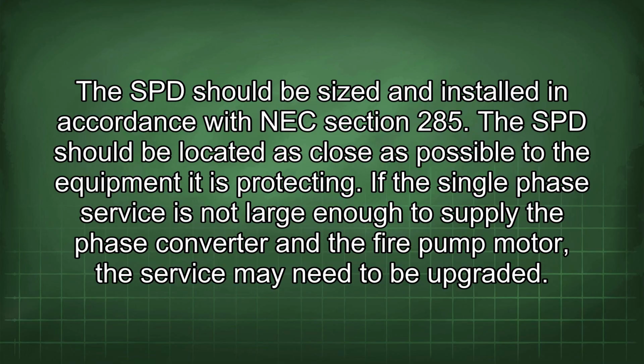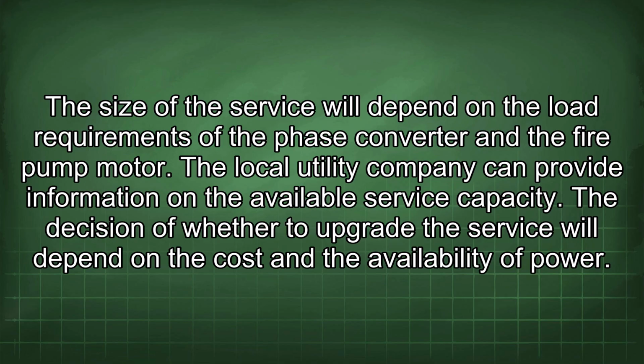If the single-phase service is not large enough to supply the phase converter and the fire pump motor, the service may need to be upgraded. The size of the service will depend on the load requirements of the phase converter and the fire pump motor. The local utility company can provide information on the available service capacity. The decision of whether to upgrade the service will depend on the cost and the availability of power.